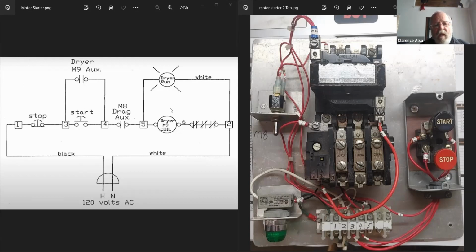I'm sure you've been through that. So yeah, I'm telling you that on the 3 side, you have 120, and when you push this and it's there, that's good, as long as you don't press the stop button. Now you press the start button, and I'm saying that you're gonna have 0 there. When you press the start button.